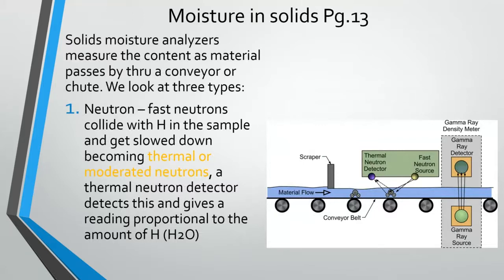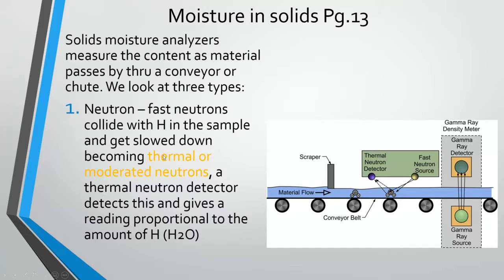Measuring moisture in solids: solid moisture analyzers measure the content of material as it passes by on a conveyor or through a chute. There are three types, all similar in basic approach: material flows on a conveyor, a scraper maintains a consistent depth of the medium, and the measuring device emits some form of energy that is absorbed by the hydrogen in the material, with the difference detected as a measurement.